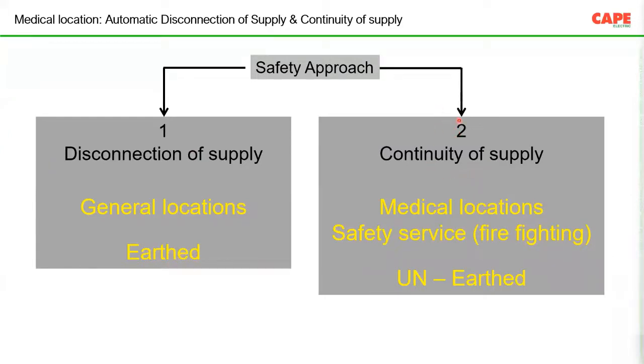The application number 2 is continuity of supply. What does it mean? In a hospital, especially in a group 2 medical location where operations happen or the patient is connected to various biomedical equipment, imagine you are putting a new device into the circuit which is faulty. Without knowing the problem, you have put the device into the circuit and the MCB tripped.